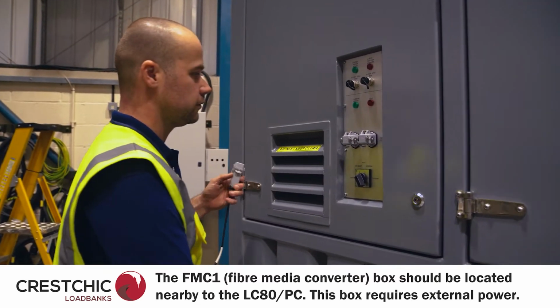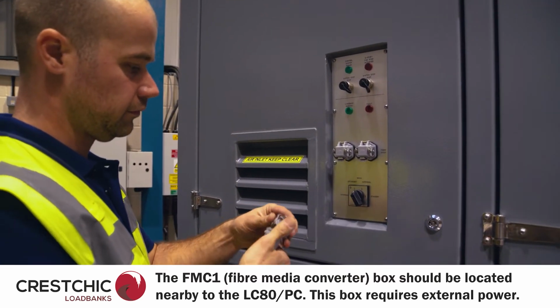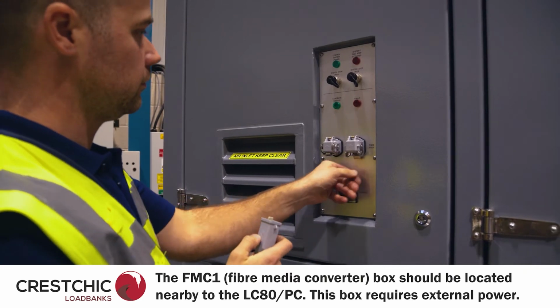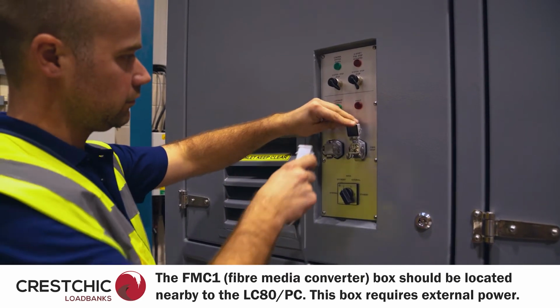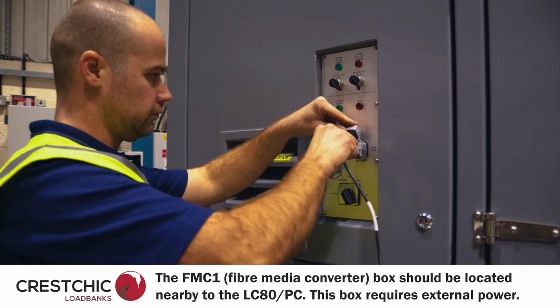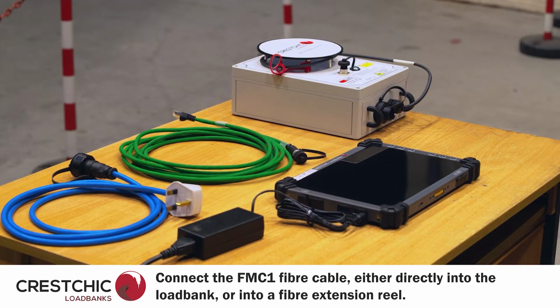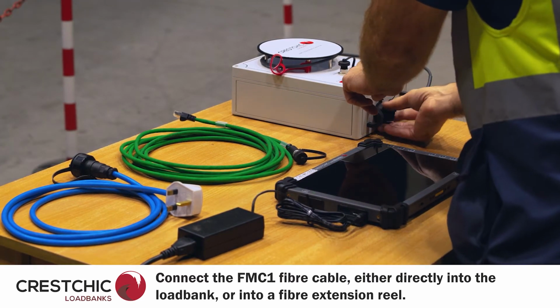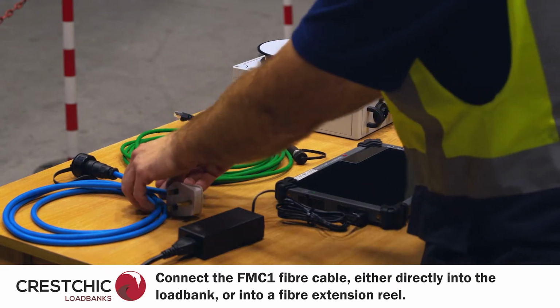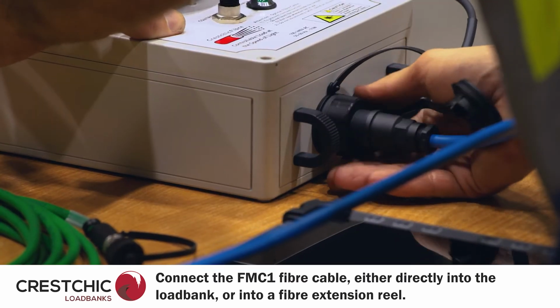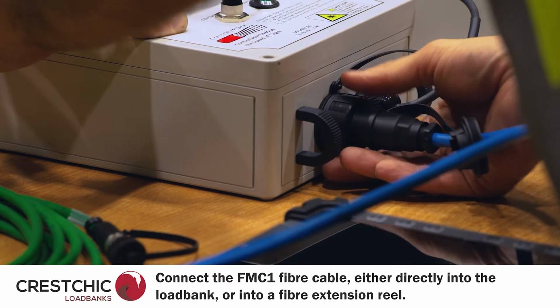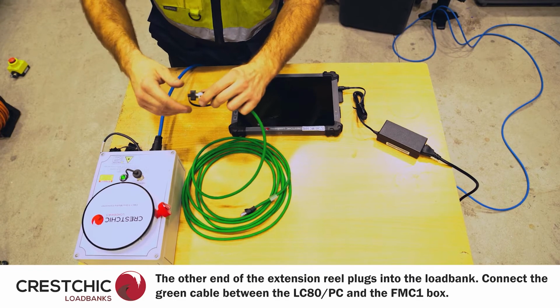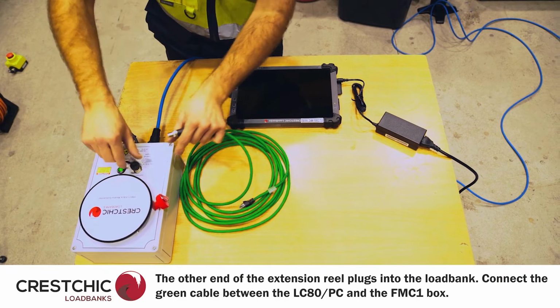It is likely your load bank will be using the new fibre connectivity. With the LC80 or PC, a media converter box called an FMC1 is required. This should be located nearby to where the controller is and will require mains power. The load bank controller can be located a substantial distance away from the load bank if required, for example in an office or control room.